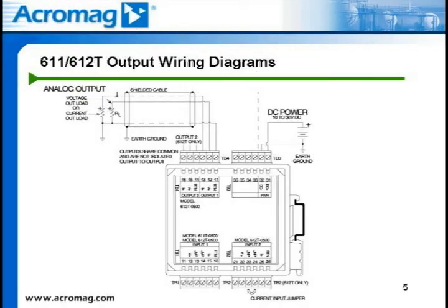The output supports current ranges from 0 to 20 milliamps DC and voltage ranges from 0 to 10 volts DC. The current output may drive up to 550 ohms, and the voltage output has a compliance of 10 milliamps maximum with short circuit protection. Here, we show the analog output wiring diagram for the 611T and 612T transmitter. Separate terminals are provided for the voltage or current output. The voltage and current output is generated simultaneously, but the channel can only be calibrated to one output range at a time. Dual channel outputs on the 612T share the common and are not isolated from output to output.